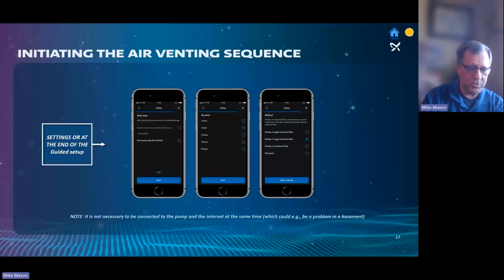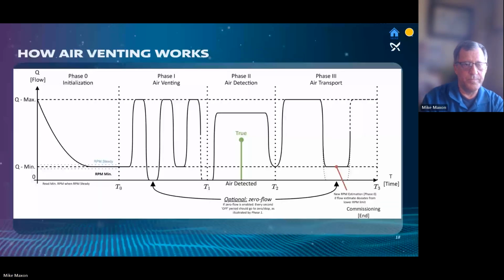And then what the pump will do is it'll pulsate to that maximum flow, to the minimum flow, to the maximum flow. We know what that does is it compresses and decompresses those air bubbles and pushes them out the air vent of the whole system much faster. Since this is going to be doing this for an hour or so, you don't have to be there watching it and nursing it. You could just have it do this.